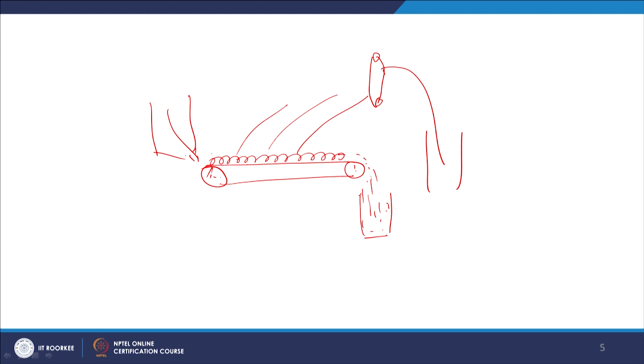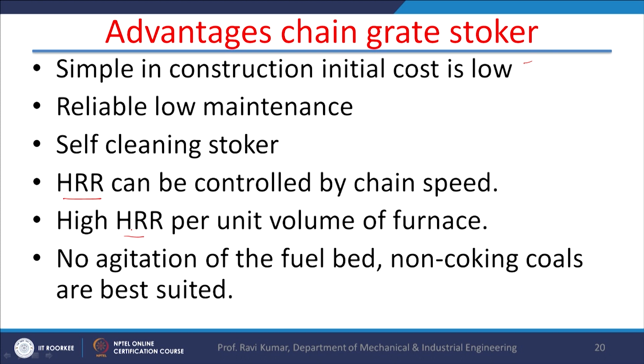So, the advantages of the chain grate stoker are that it is simple in construction, the cost is low, it is reliable, maintenance is low, and it is a self-cleaning stoker. Heat release rate can be controlled by chain speed, and a high heat release rate per unit volume of the furnace is possible. There is no agitation of the fuel bed, so non-coking coals are best suited for this purpose.